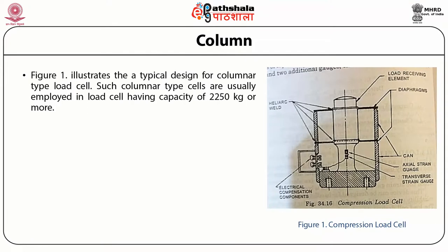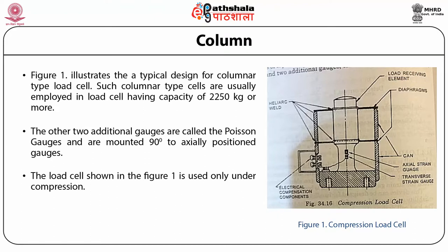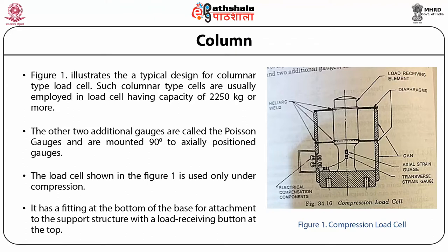First is column. Figure 1 illustrates the typical design of the columnar type load cell. Such columnar type cells are usually employed in load cells having capacity of 2250 kg or more. It has two strain gauges called active gauges that are bonded axially. The other two additional gauges are called Poisson gauges and are mounted 90 degrees to the axially positioned gauges. The load cell shown in Figure 1 is used only under compression. It has a fitting at the bottom of the base for attachment to the support structure with a load receiving button on the top.